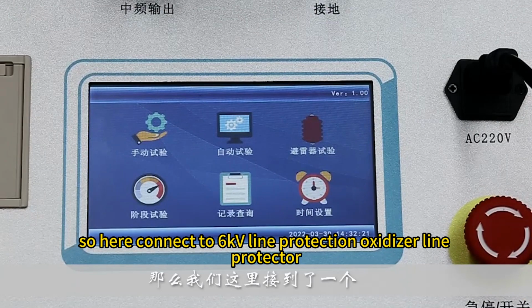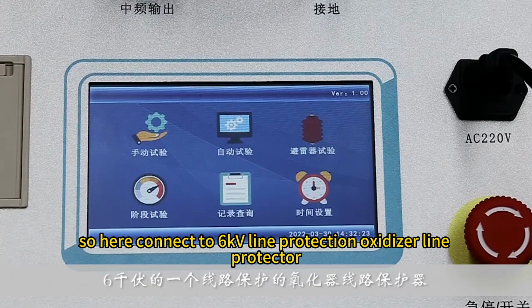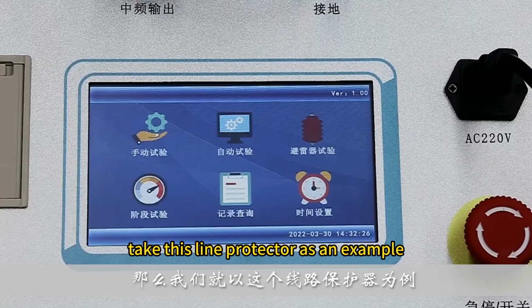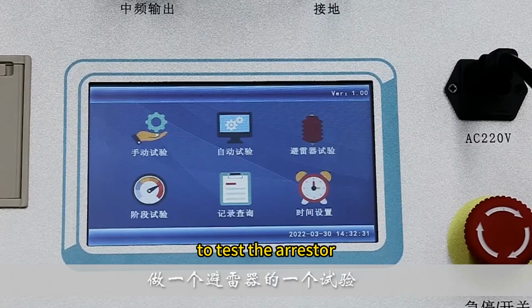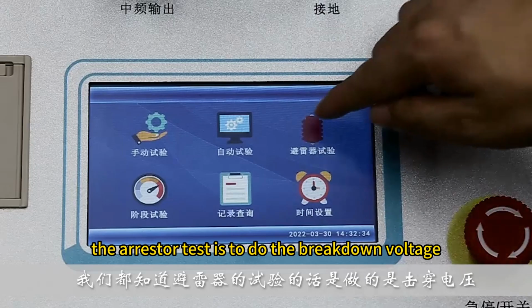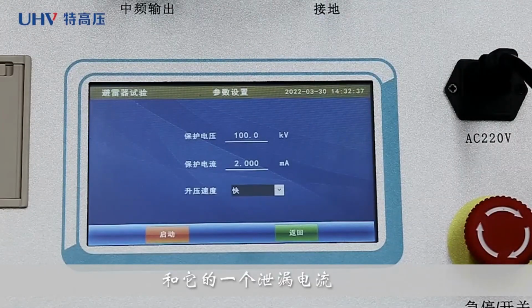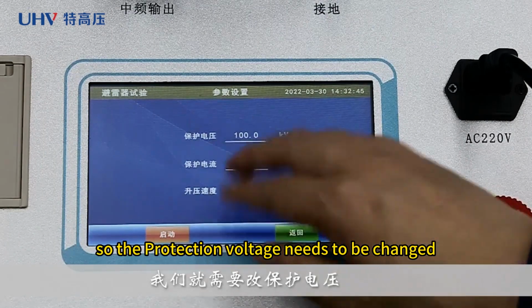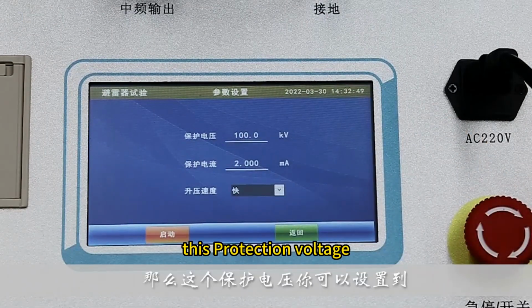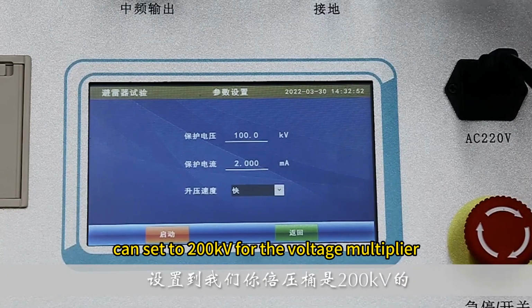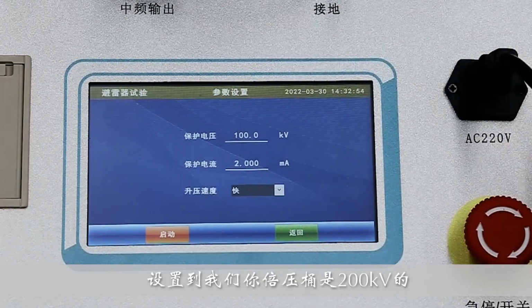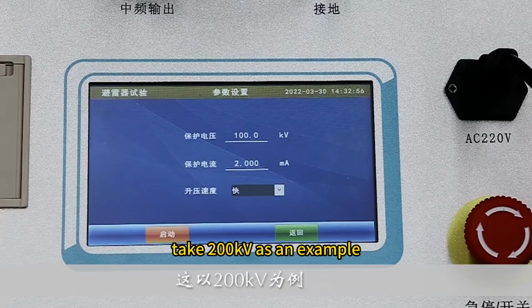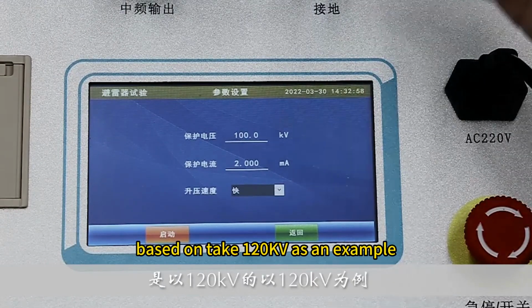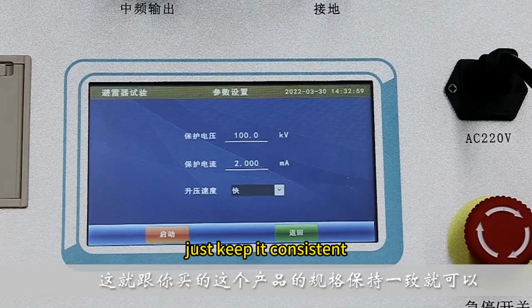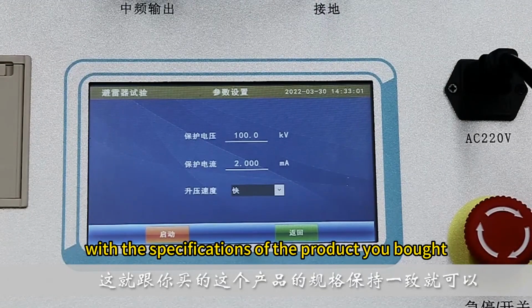So here I connect a 6 kV line protection oxide arrester. Take this line protector as an example to test the arrestor. The arrestor test measures the breakdown voltage and leakage current. So the protection voltage needs to be changed. This protection voltage can be set to 200 kV for the voltage multiplier. Take 200 kV as an example, or 120 kV as another example. Just keep it consistent with the specifications of the product you bought.